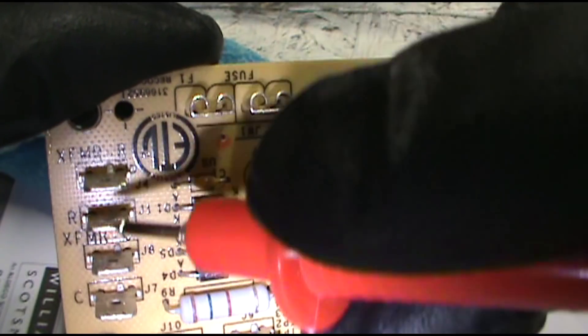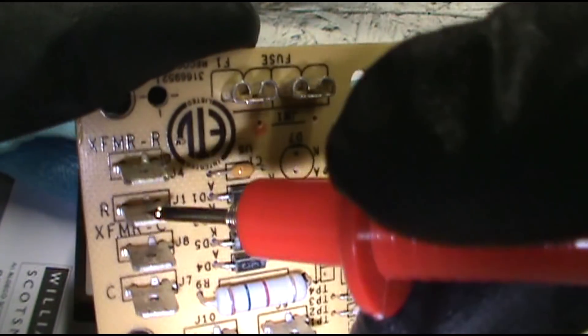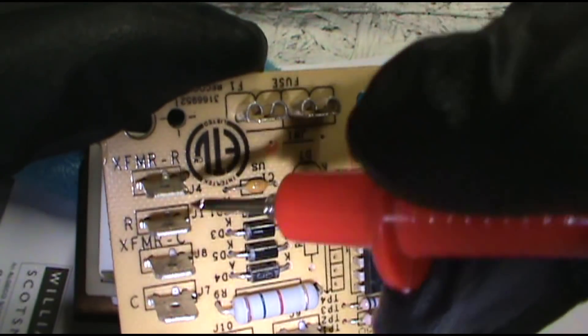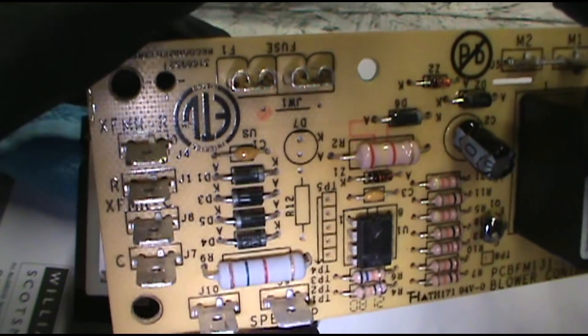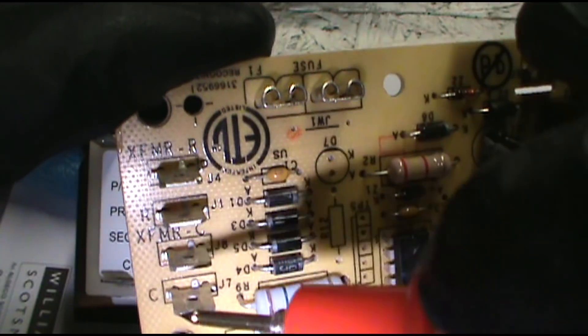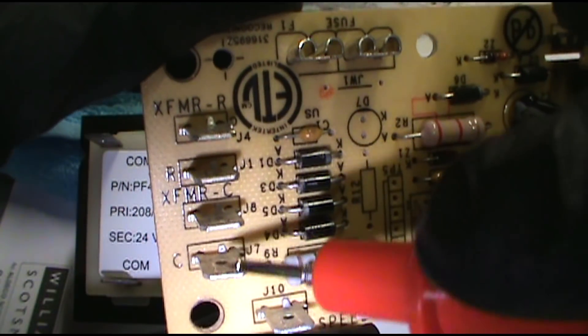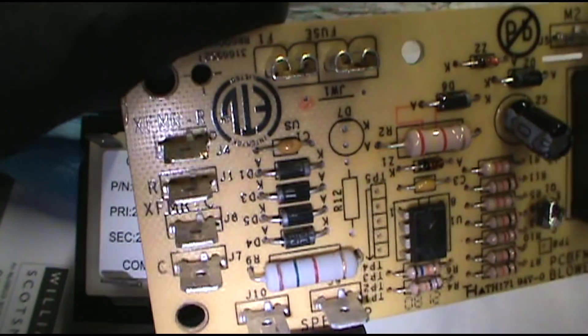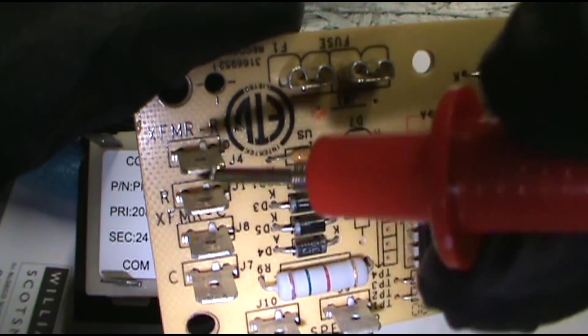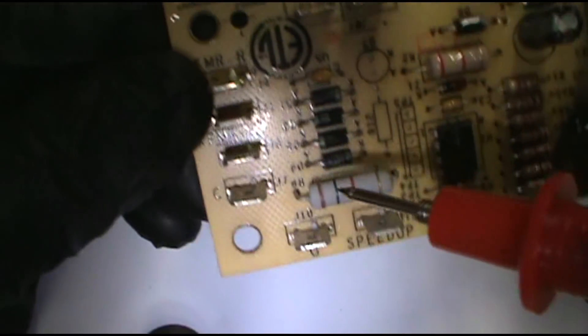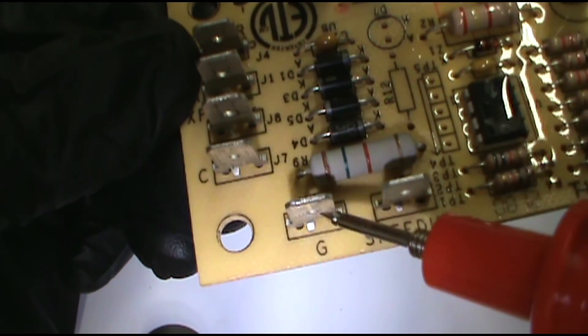And this R here, the second terminal, is the power coming out and feeding the field wires. It'll come out and go down and connect to your little red wire, feeding the 24 volts to the field. Same with common on the Goodman. This is usually a blue wire. It comes out and feeds the common wire to the field wires. So in, out. And this G here, it's usually going to be a green wire.